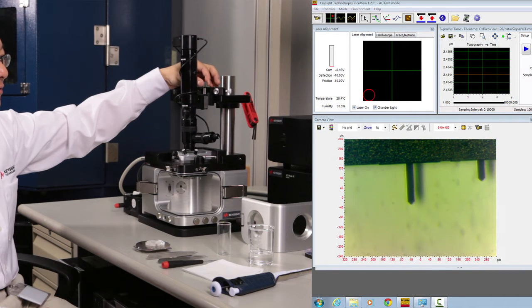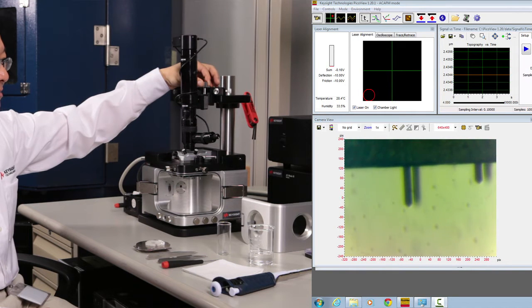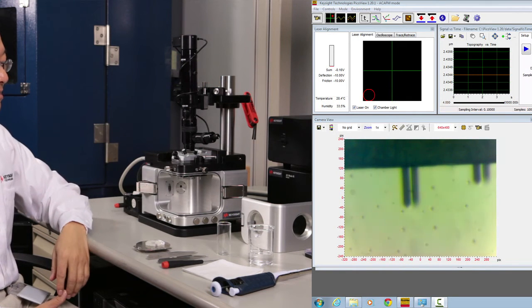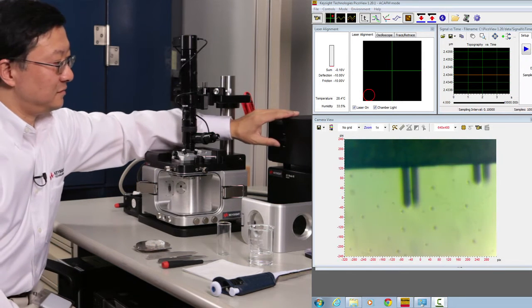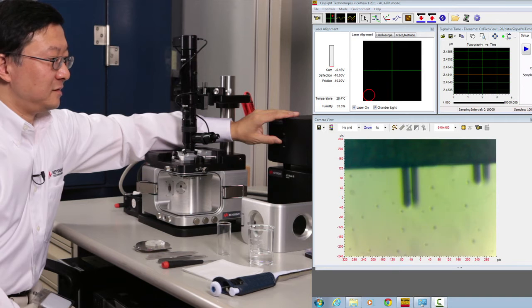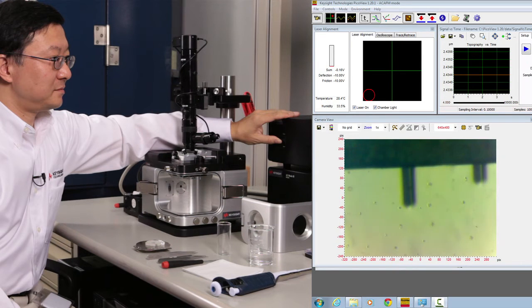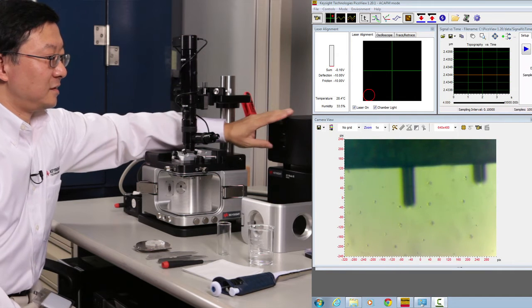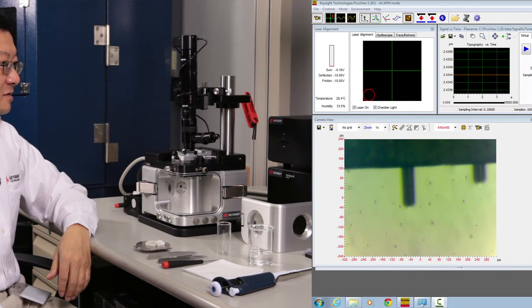Here's how to do that. You focus on the tip and focus down a little bit until you see two images of the tip. And then we use the manual approach to move the sample up until the two images overlap with each other, and we know that the sample is very close to the tip. Now, as we can see, the two images are very close to each other, and therefore we can say the sample is very close to the tip. Remove this alignment sample.